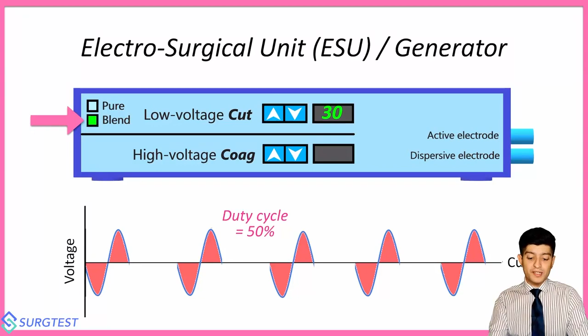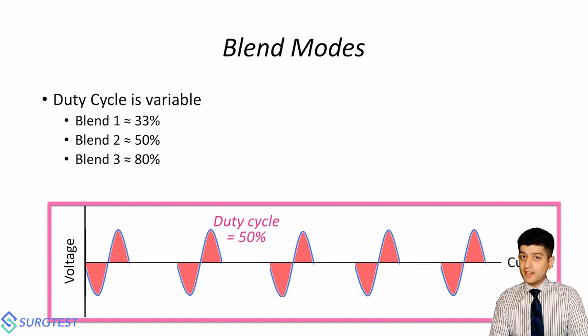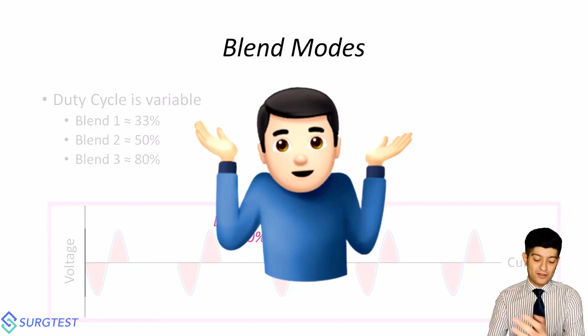So duty cycle in blend modes is extremely variable. In most machines that have different blend modes designated, the first one will have a duty cycle of 33%, the second one will be on average 50%, and the third one will be close to 80%. Now again, notice that these are all approximations and the actual figures may vary depending upon which ESU or which company you eventually end up using. So I can't be sure what exactly is happening in your ESU. You're going to have to look at the manual or go through all of the settings yourself. Usually the blend mode duty cycles are not shown on the displays of these ESUs and you have to go back to their manuals.